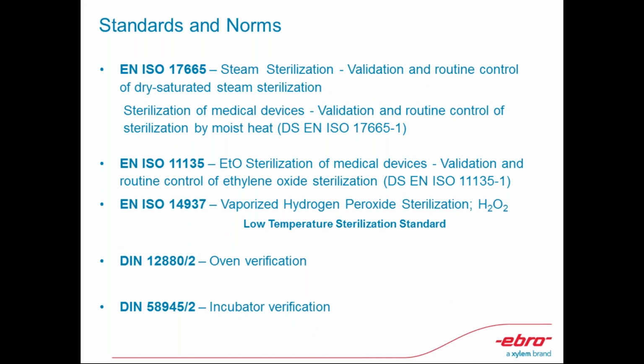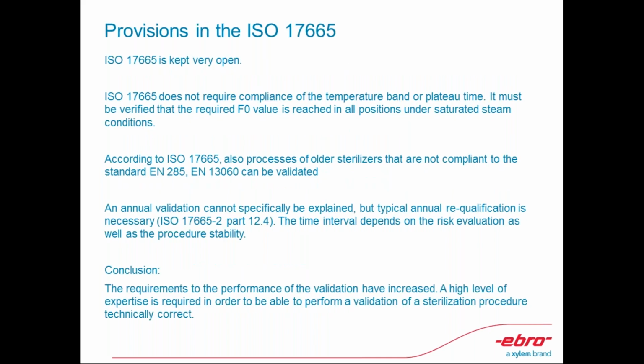Long ago, there were no regulations for hydrogen peroxide, but now we have ISO 14937 specifically for low temperature sterilization standards. And this is a good read. I find it a very good read. So I'm recommending that you browse through this standard when you have the time. And in the pharma and healthcare, we also have different standards and norms for ovens and incubators. We talked about this last session, but ISO 17665, when it comes to sterilization, is the most common standard observed across the globe.